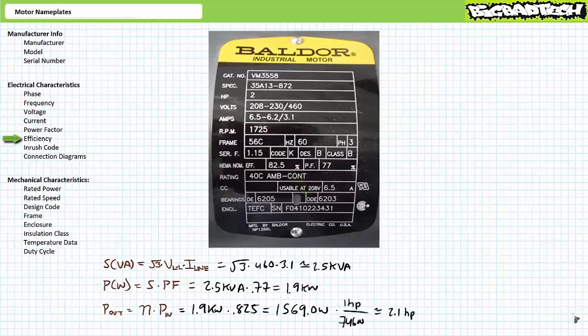A unit conversion demonstrates roughly 1.9 kilowatts is equivalent to roughly 2.1 horsepower, extremely close to the nominal or nameplate value of 2 horsepower, as one might expect. It's a 2 horsepower motor. As with current, power factor and efficiency entries on a motor nameplate are specified at full load conditions and will vary considerably over the operational range.